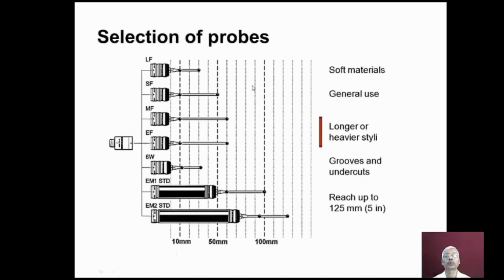Now how do we select the probes? Depending upon the material. If you have a soft material, then we should select probes with low measurement force requirement. For general use, we can select the SF type, and for heavier, longer styli we should use probes with medium force requirement. Similarly, for grooves and undercuts, depending upon the type of inspection, we should select probes of appropriate length with appropriate force requirement.